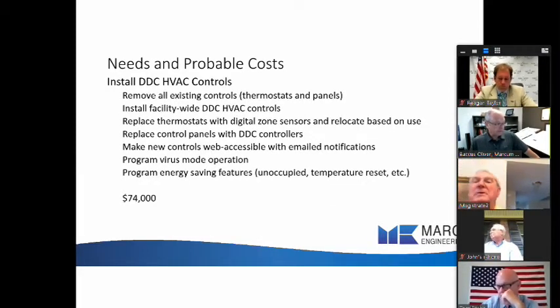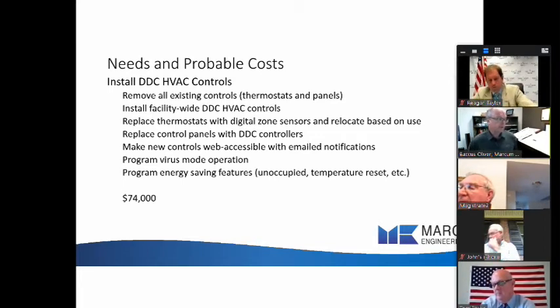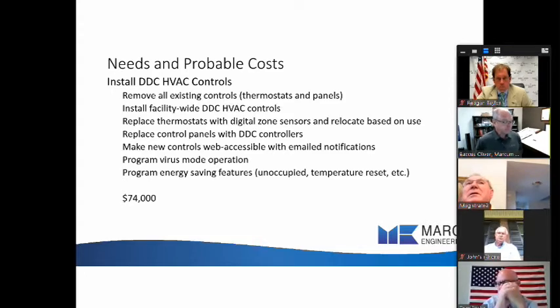Next in order of rank, I would install DDC controls. That's basically a digital control system. I would remove everything that's there. I would install a facility-wide digital control system, replacing all thermostats and all the panels with controllers. This would be a computerized control system that's web accessible and that will email or text notifications when there's a problem. That helps maintenance know that they need to go and investigate something before it becomes an even bigger problem. We can program this unit for what's now popular, and that is a virus mode. And we can even look at putting ultraviolet light in the unit to help make the air safer for the occupants of the building. And then the last thing, most importantly, is we can program for energy savings.